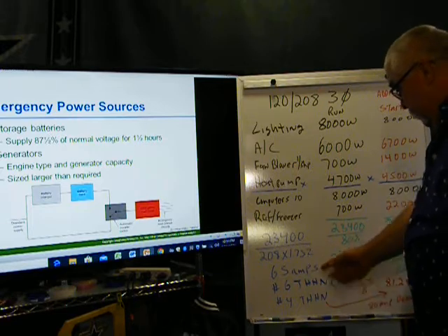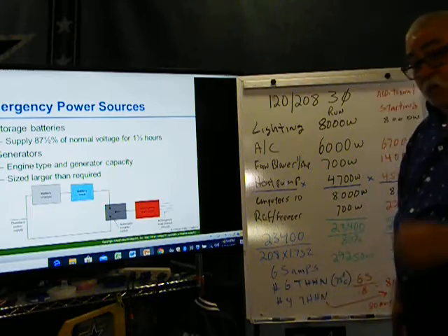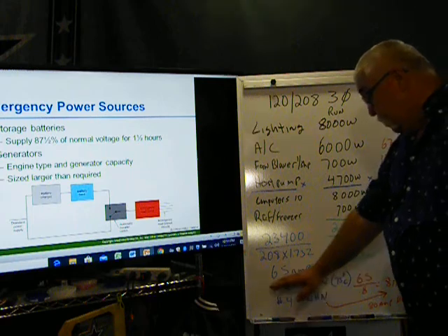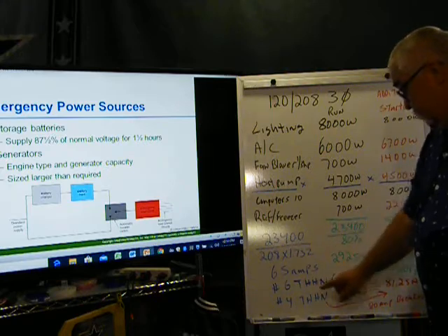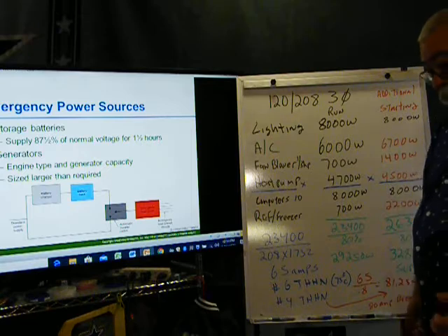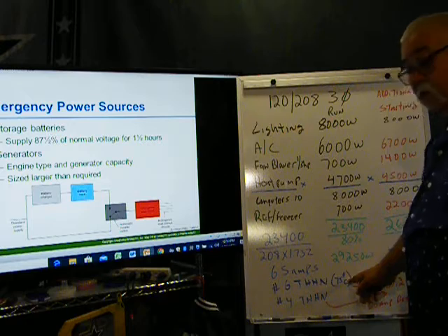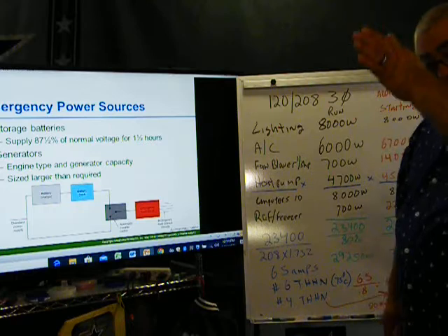Okay, add everything up, find your ampacities, then take it up to 125%. So if I'm at 65 amps, I want my wire size to carry 125% of this. How do I get that? I divide my amperage by that 80%, and then that'll give you the amperage for your wire size. Go into the 75 degrees C, because you are talking about a feeder. It doesn't matter if it's 100 amps or less. Look at that 75 degree. Pick that, and then that's your wire size.